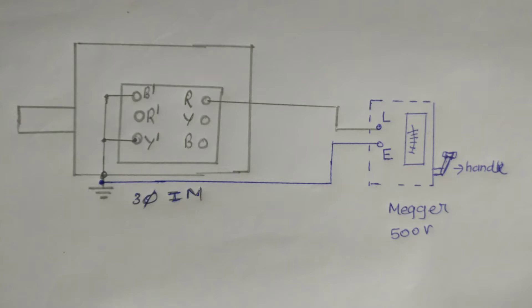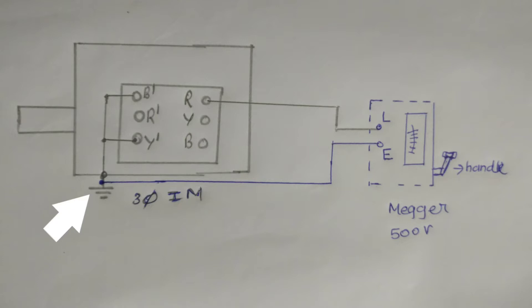This is the terminal connection. This R terminal and this R' terminal — we are measuring the insulation resistance of the R phase winding with respect to earth, that is the insulation strength of that winding. Between R and earth, we have connected the megohmmeter. As per the procedure, the other windings have to be connected to earth also. So the Y winding and the B winding are shorted to each other and that short connection is connected to the earth itself.